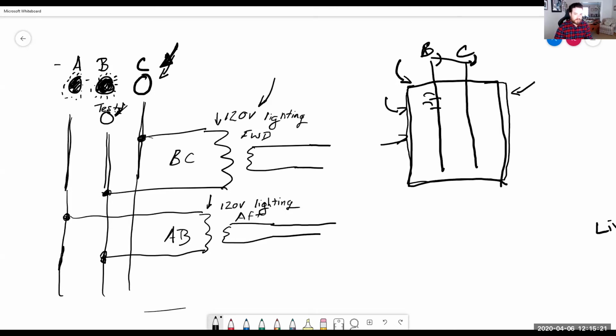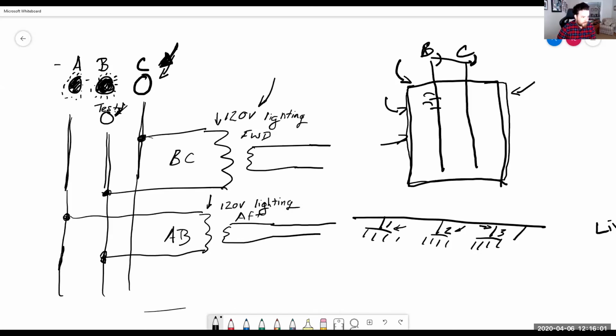Once this light goes on, and after going through phase C, which has all these different breakers, you might have breaker panel 1, 2, 3, and so on. After switching panel 1 off and the light doesn't go off, you turn it back on and go to breaker panel 2. You switch it off, and if the light doesn't come back on, you know the ground isn't in 2. You finally get to panel 3, switch off the breaker, and the light goes back on. Now you know your ground is on phase C, breaker box 3.